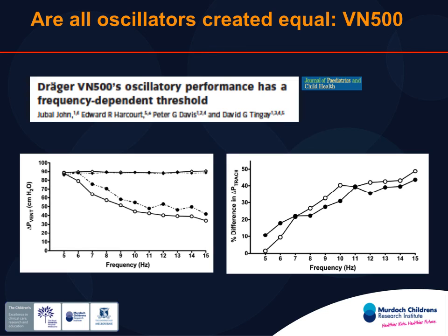With the VN, at least in the test lung, and this is an IE ratio of 1-to-1, and this is an IE ratio of 1-to-2, there was a relationship between the frequency and the delta P the device actually generated, despite what it was set at. And again, this isn't a limitation of the device. What it means though is if you were going to use a frequency of 15, theoretically you may not be able to generate a delta P of 40 or 50 if that's what you need. That's not too different from what we already know about the Babylog. We've always known with the Babylog that sometimes if you want to use it more efficiently, you have to use a frequency a couple of hertz lower.